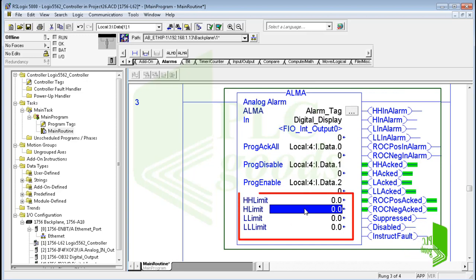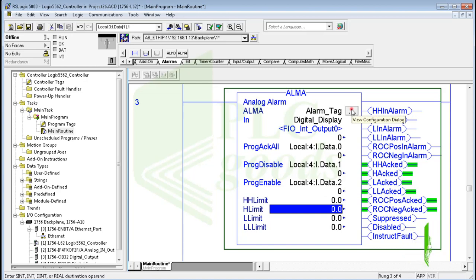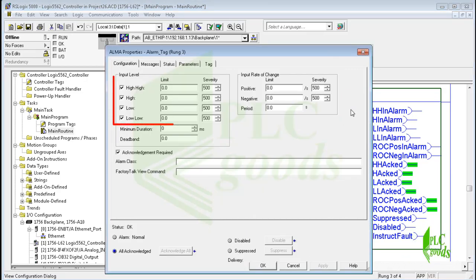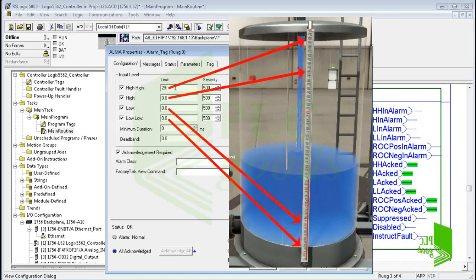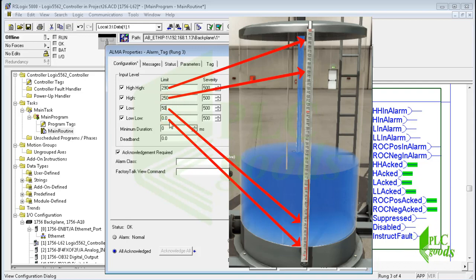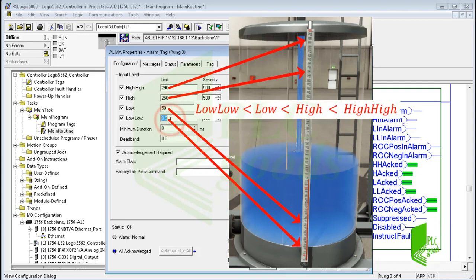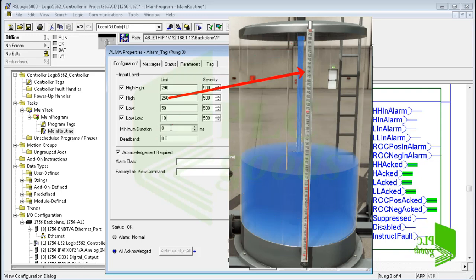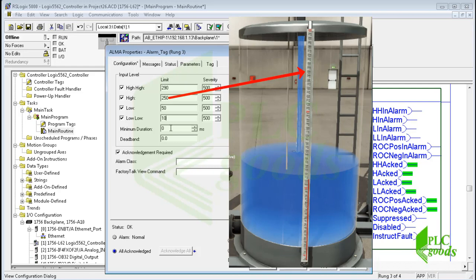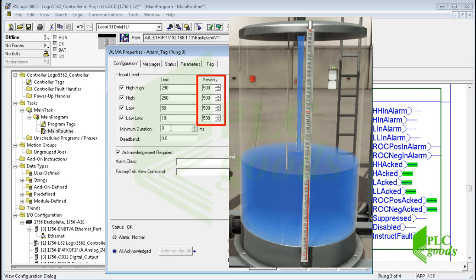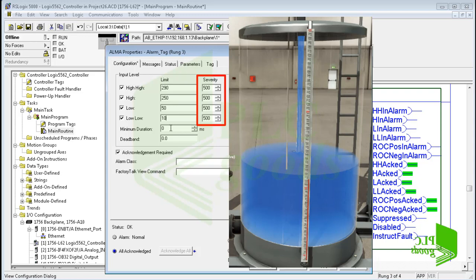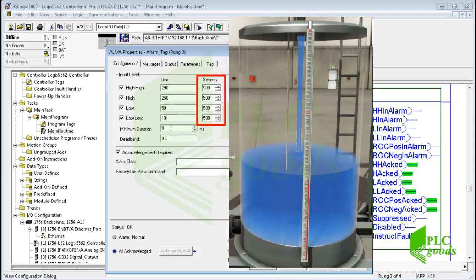Then the high and low alarm limit must be defined here or inside the alarm properties windows. In this project, these parameters are the high and low limit of the water level. They can be a number between 0 and 300 centimeters. Naturally, the entered values must satisfy these inequalities. For example, if the water level exceeds this level, a related bit inside the alarm tag will be changed to 1. Note that you can enable or disable each alarm condition or change its severity. Severity does not affect processing of alarms by the controller, but can be used for sorting and filtering alarms. It can be a number between 1 for the least severe and 1,000 for the most severe alarms. Its default value is 500.